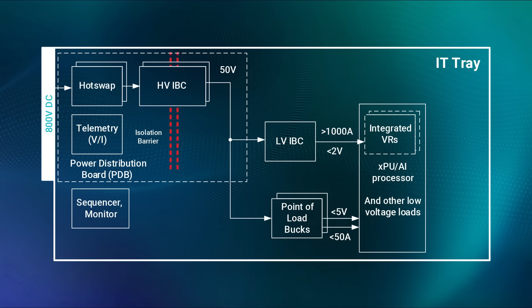Lastly, another potential future trend that we see is integrated voltage regulators. This is actually placing the voltage regulators inside of the AI processor package. How that's going to impact processor power delivery is that you might decide to keep the output voltage of your IBC to maybe 50 volts. And then you'd have a 50 volt down to some low voltage, maybe 1.8 volts, that would be the input to your integrated voltage regulators. This has the benefit of really getting that multi-phase VR as close as possible to the processor, thereby increasing performance.